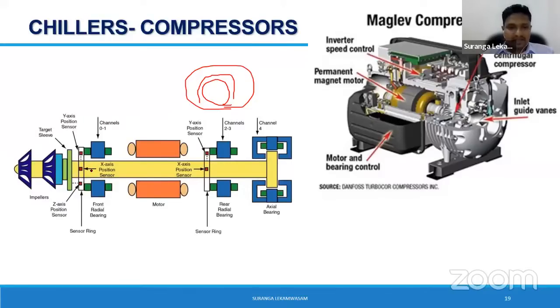So, addressing all these issues, people invented this oil-free compressor where your shaft is floating within a magnetic field, right? You can see there are different magnetic fields lifting the shaft. There are position sensors to check the position in real time. Likewise, there are many advanced features on these magnetic bearing chillers. In addition, they have improved their motor. You can see it's a permanent magnet motor. Actually, this is a synchronous motor where you can go for very high RPM. Typically, the rated speed of a magnetic bearing compressor is closer to 40,000 RPM, which is very, very high, because they have synchronous permanent magnet DC motors.